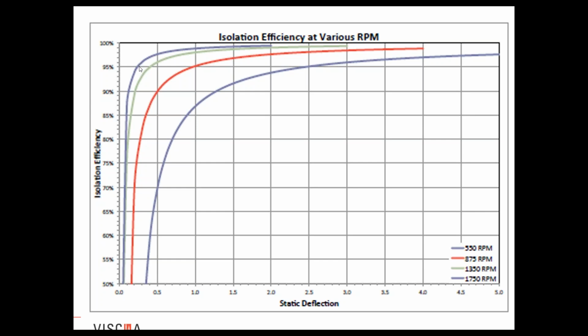So as John was illustrating earlier, it is an indirect proportion. If you're looking at a static deflection of 2 inches with the 550 revolutions per minute, you're going to be at 93, 94% isolation efficiency. But you'll obtain that same 93, 94% isolation efficiency if we look at the green at the 1,350 revolutions per minute, with now probably a static deflection of less than half an inch, probably around a quarter of an inch or so. So again, it's an indirect proportion, but it's good to know what the isolation efficiency looks like for various RPM, various revolutions per minute.